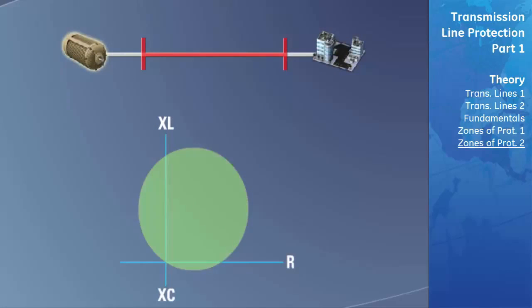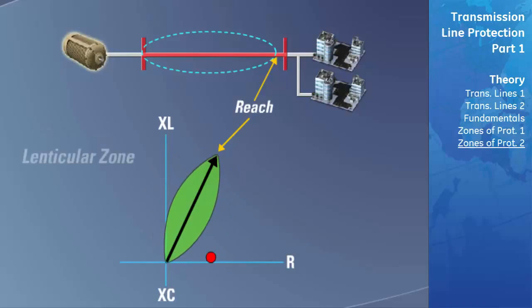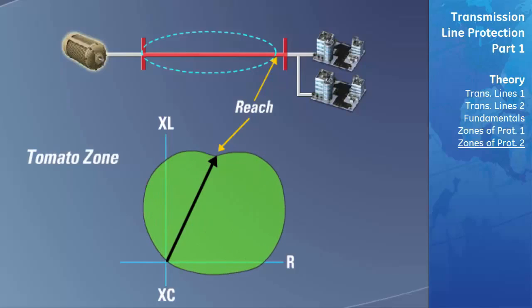Advanced microprocessor-based relays such as the UR D60 give the user the ability to further customize the shape of the Mho circle to meet their protection needs. For example, if the power system has instances where it can be heavily loaded and may cause the impedance to encroach into the Mho circle, the area of the circle may need to be changed. The Mho zone can be altered to form a lenticular shape, which only allows tripping when the impedance falls very close to the angle of the transmission line impedance. The D60 relay also gives the protection engineer the ability to configure the Mho characteristic into what is known as a tomato-shaped zone, which allows for faults with more of a resistive element to fall into its zone of protection.